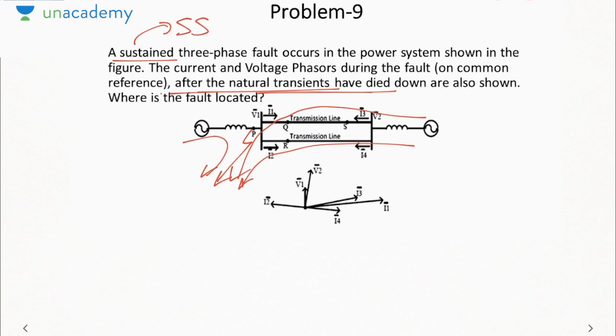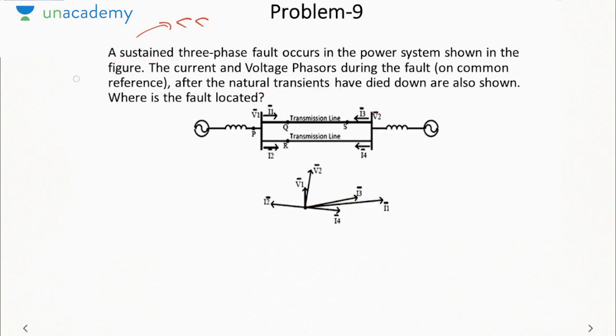So now I2 satisfies the criterion that I2 should be from right to left, but I1 is from left to right and it is lagging the voltage, so that means the direction is correct. Since I1 is lagging the voltage, that means the direction shown is the same as the direction assumed, or the direction shown is the same as the actual direction. Hence, I1 cannot be reversed, so P cannot be the fault location. If P were the fault location, I1 as well as I2 would be reversed and both would be leading the voltage.